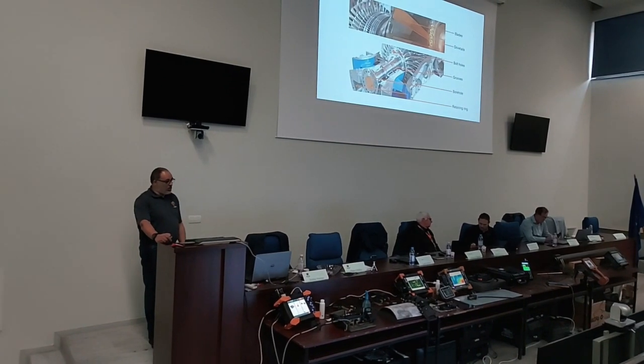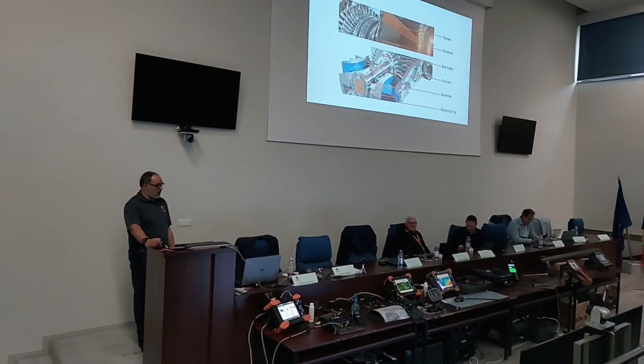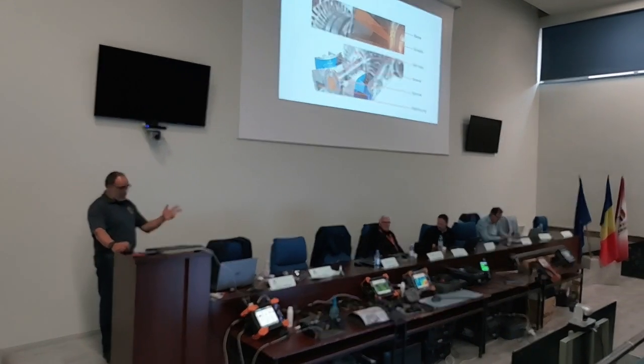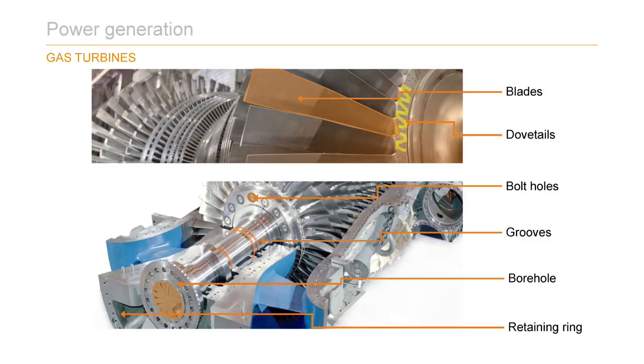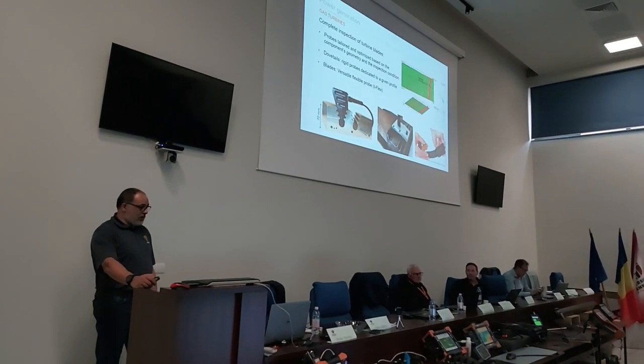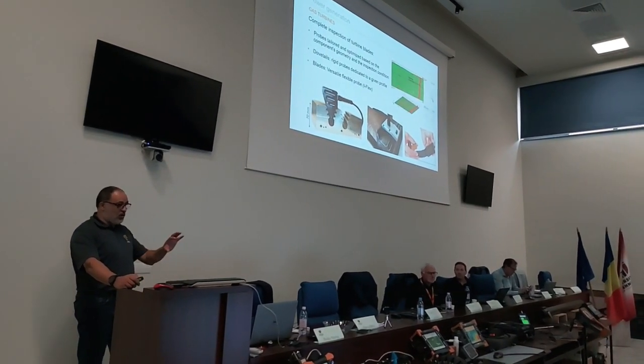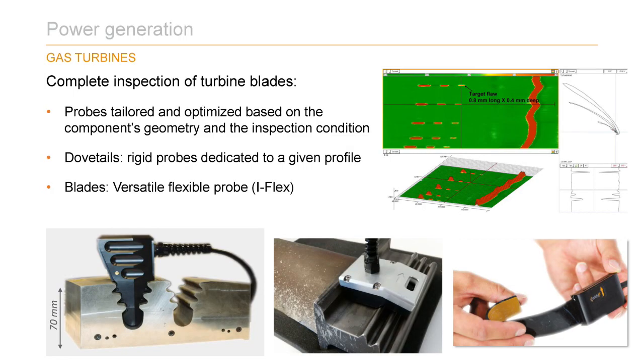Here's a quick overview of what we can do on power generation: gas turbine inspection, so it can be the blade, the dovetails, the holes, grooves, etc. We have dedicated probes for that, you can see here an example. And on top right of the slide, an overview of a calibration block, that calibration block that you will use to set up your equipment before starting the inspection of your parts.